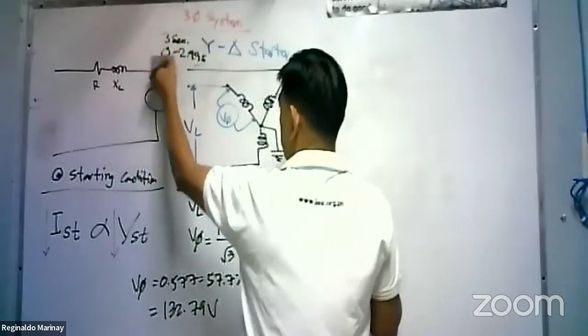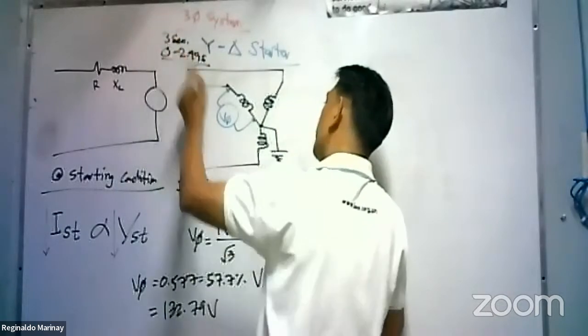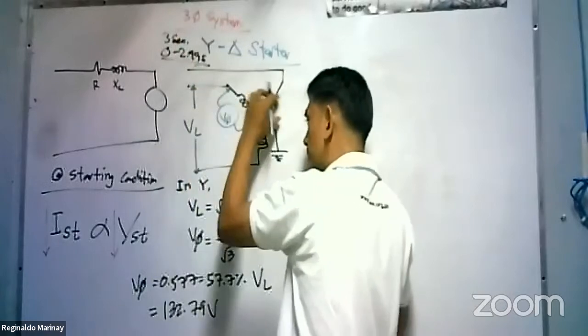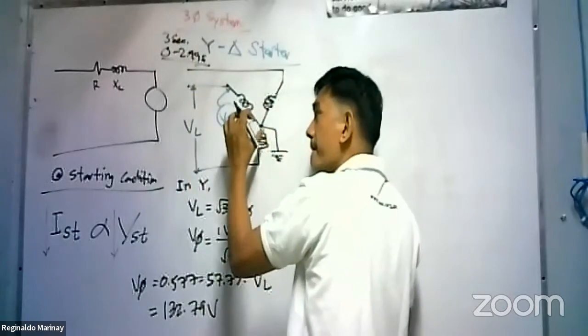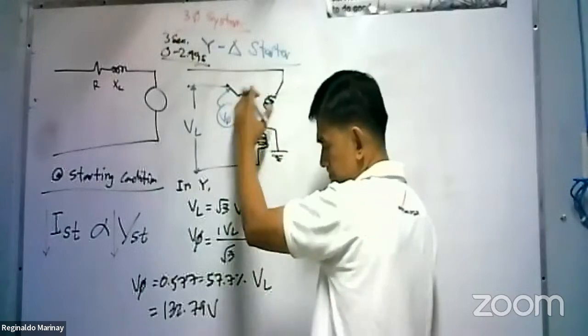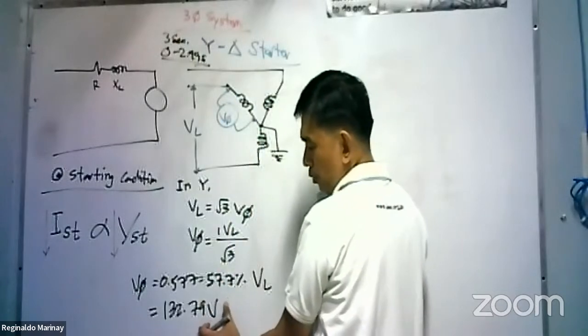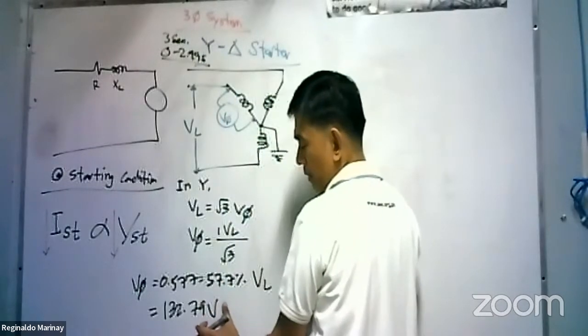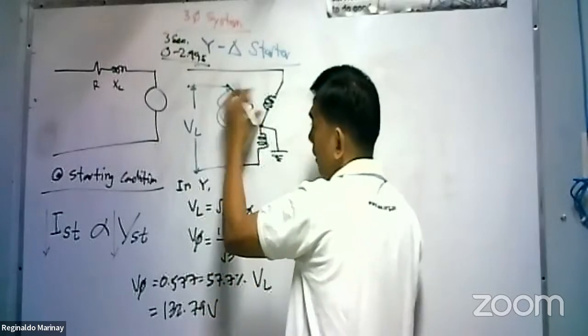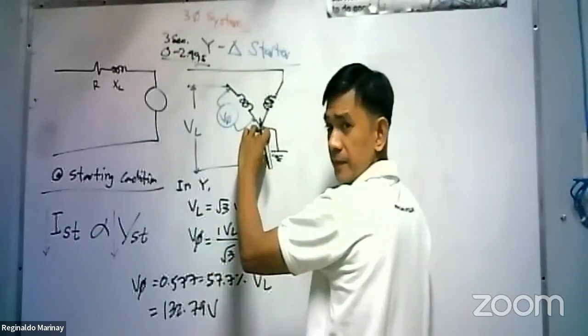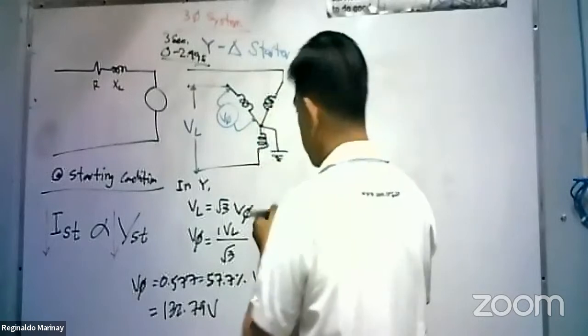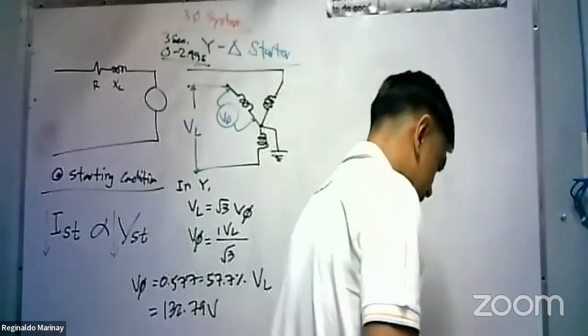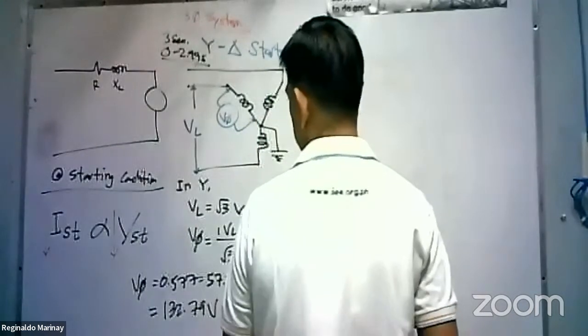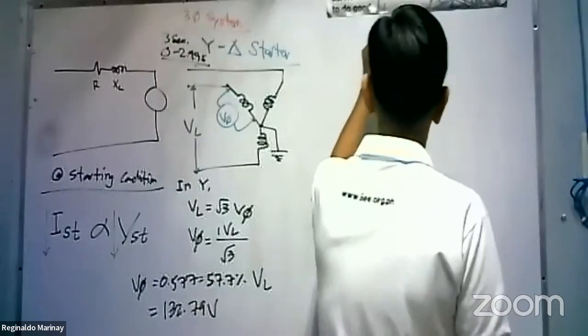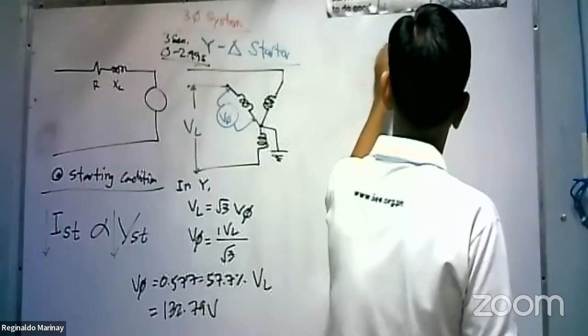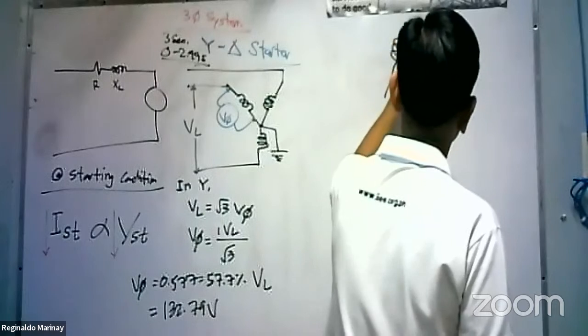So from 0 to 2.99 seconds, the winding of the motor is connected in Y. See? 132.72 volts is approximately the voltage of the coil of this motor. Once you reach 3 seconds, it will become delta. It will become delta. Take a look here.